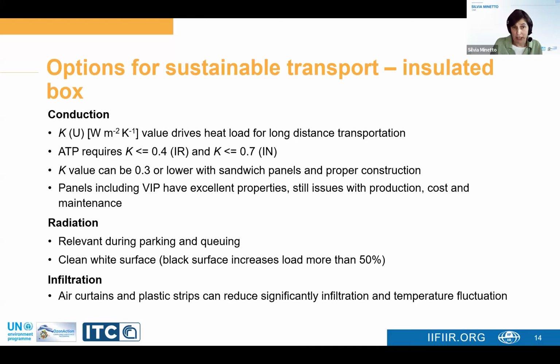I've not mentioned the radiation so far because it is not relevant when the system is moving. So when the truck is moving, there is a balance between the radiation load and the external convection, which is removing the excess heat. But radiation can become a challenge during parking and queuing. So a clean white surface needs to be adopted because it has been demonstrated that a black surface can increase the load by more than 50%.